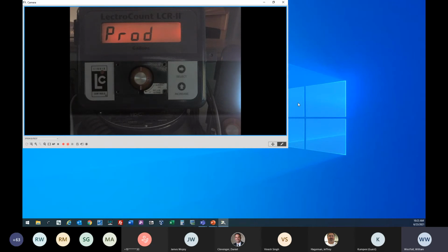But in this case, we've only got product number 1, so we will go ahead and select it. Now you're seeing your flow rate. Since we aren't delivering anything right now, our flow rate is at 0. If we hit the select key again, now we're going to get our temperature. This one doesn't have a temperature probe installed, so you're going to see this 999.9 degrees Fahrenheit. If it was in Celsius, you'd just see the Celsius sign there instead of the Fahrenheit. So you go one more, and then you go back to your counter.